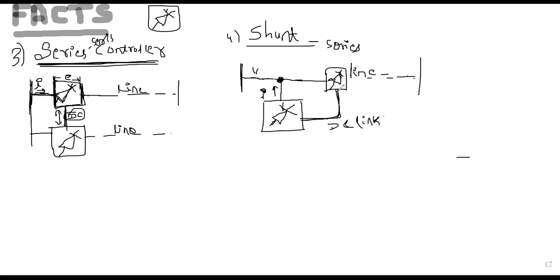This interconnected or interline system, real power exchange will happen here now. So we can compensate both real and reactive power here. The examples are called IPFC and UPFC. IPFC is interline power flow controller. UPFC is nothing but unified power flow controller. So these are the four types of FACTS controllers here now.